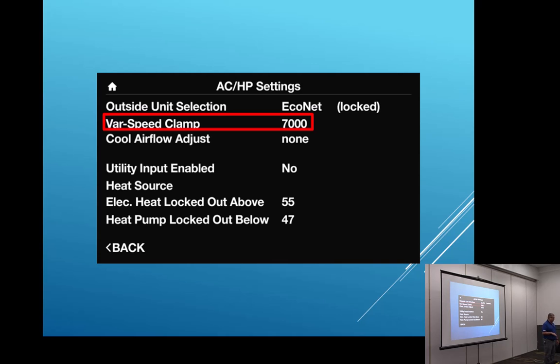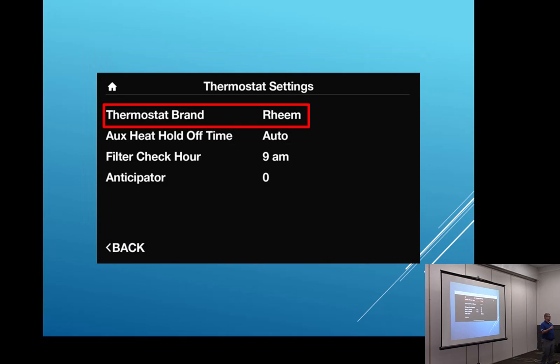But if you didn't, you can come in here and adjust this variable speed clamp. I would tell you, you could take it all the way down to about 5,000 or 5,500 RPM, and it's still going to produce above the normal. It won't produce the 120%, but it's still going to give them more capacity. But that sound is not as loud as it was before, and maybe that'll suffice them, and they don't have to look, okay, we changed it some, this is what we did, but it's still going to sound like that. So a little bit of education, but you can change it if you have a persistent homeowner, okay? You can do an airflow cool adjust there if you need to.